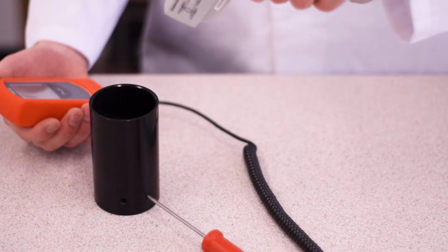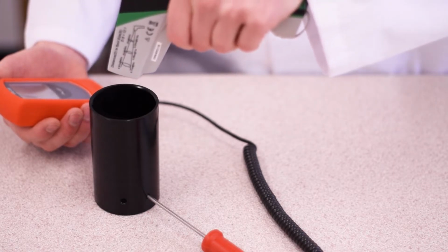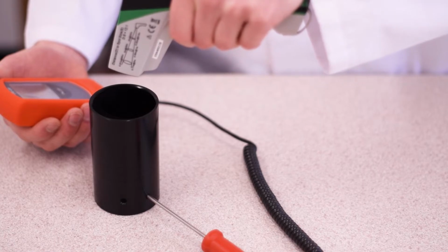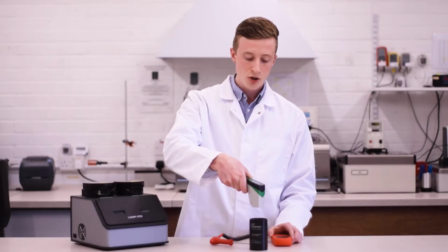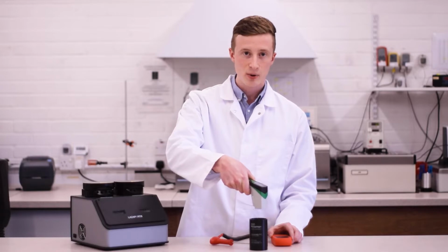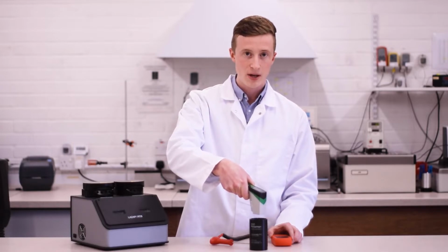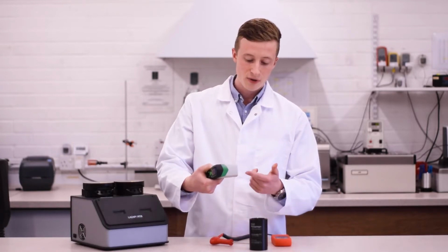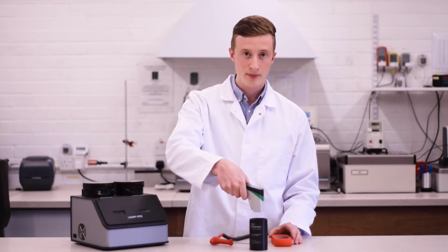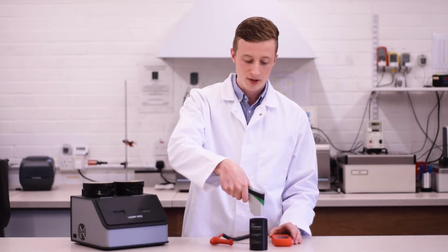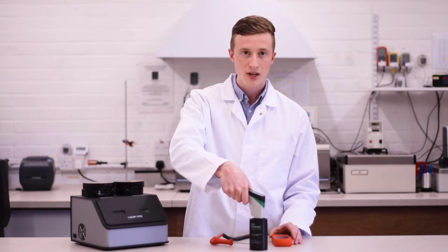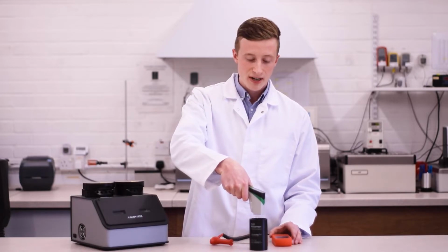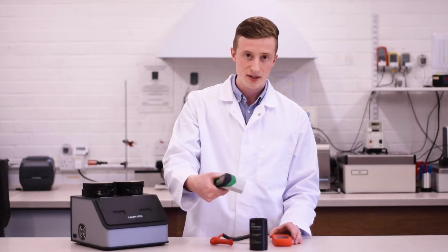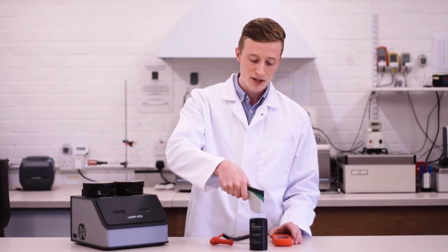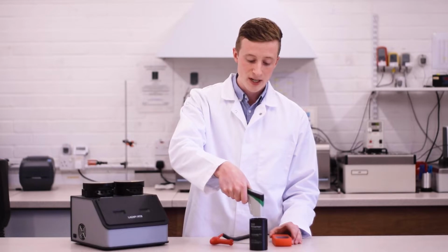Take your infrared thermometer and hold it perpendicular over the top of the comparator pot. You should be pointing it at the black bottom inside of the comparator pot. Use the laser guides on the front of the thermometer when you squeeze the trigger to help you position the thermometer correctly. Squeeze the trigger to take a reading on your infrared thermometer. We recommend taking 3 readings separately to ensure you get a consistent, reliable and repeatable reading.